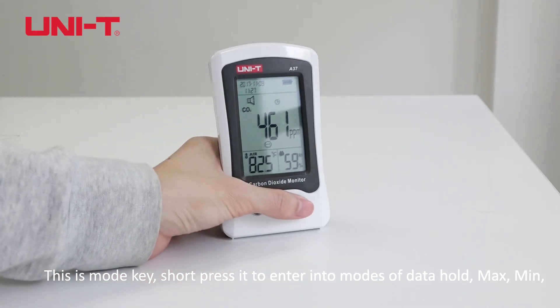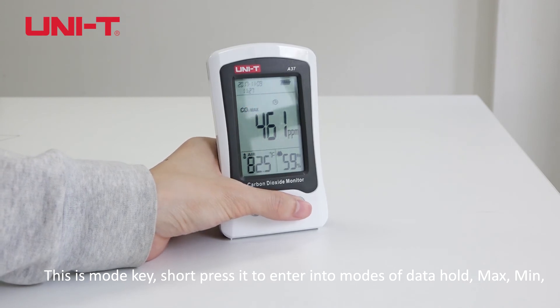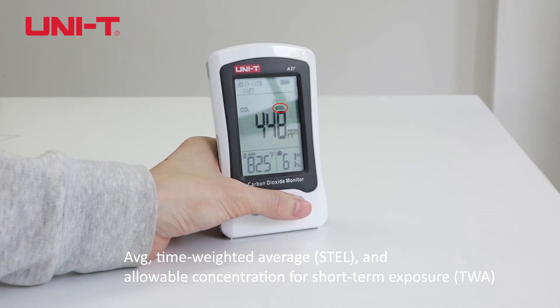This is the mode key. Short press it to enter into modes of data hold, max and minimum, average, time-weighted average, and allowable concentration for short-term exposure. Short press it to cycle through options.